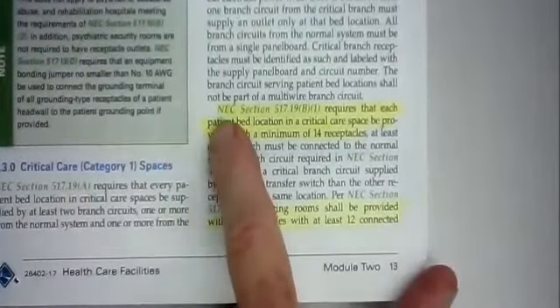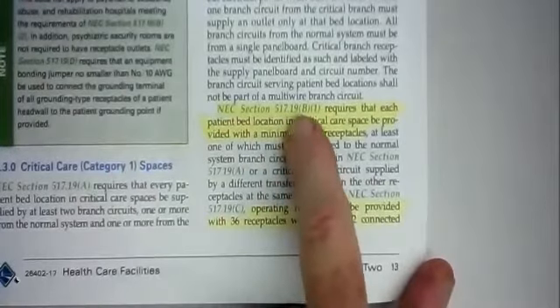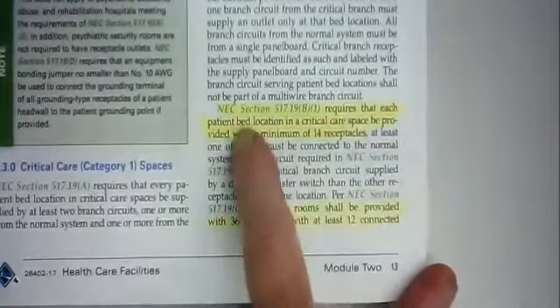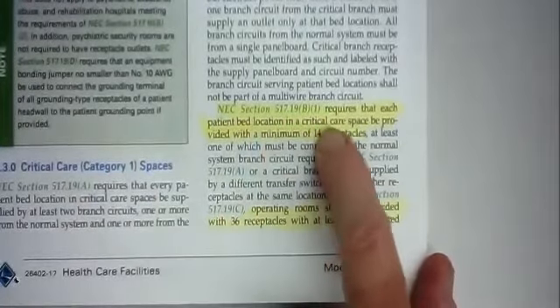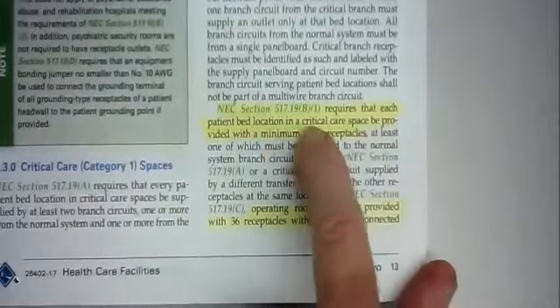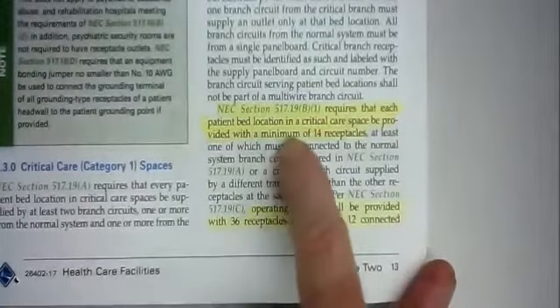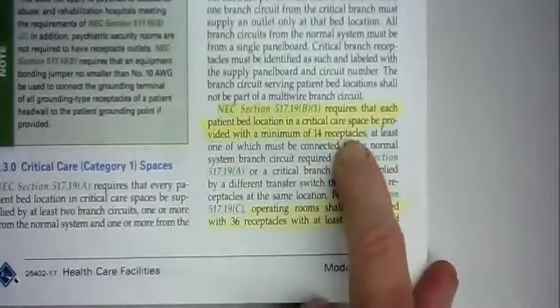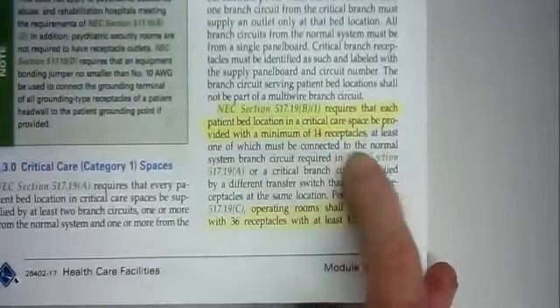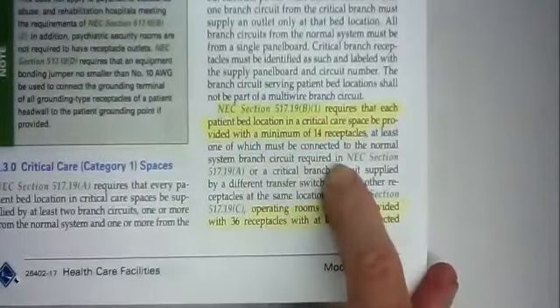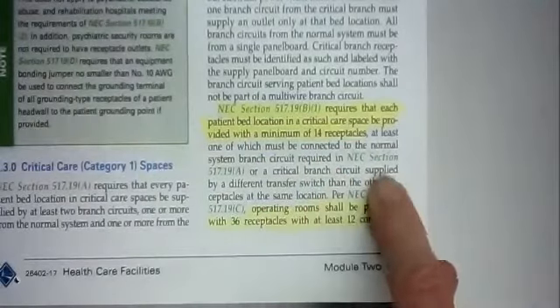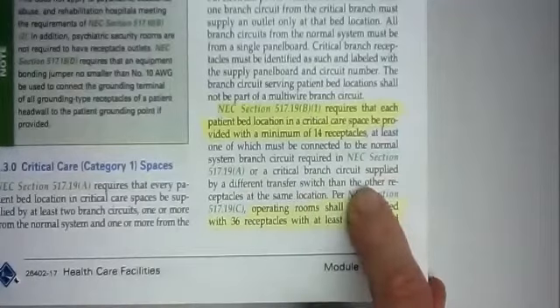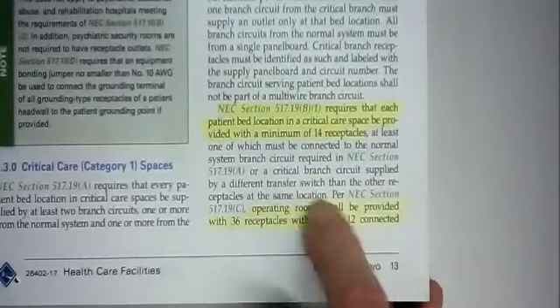On the right-hand side of page 13, right-hand column, very bottom of the page, NEC section 517.19(B)(1) requires that each patient bed location in a critical care space, there you go, critical care, be provided with a minimum of 14 receptacles. And it says at least one of which will be connected to the normal system branch circuit or a critical branch circuit supplied by a different transfer switch than the other receptacles in the same location.